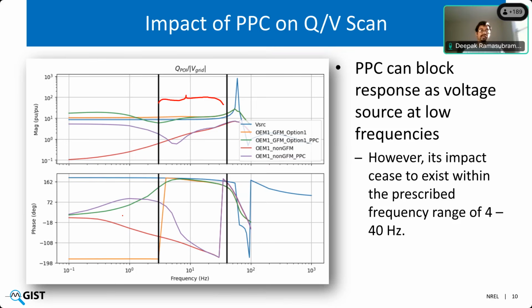If you look at it at the complete plant level, the plant controller can actually filter that behavior out in the lower frequency range, which lends more support and credence to why we're looking at that 4 to 40 hertz range: the plant controller is not dominant in that particular time frame. That is the frequency range in which we want the grid forming property to be assessed. So that provides a little more background into how the range of frequency can be determined, and also shows the effects of the plant controller if you're testing at plant level versus inverter level.